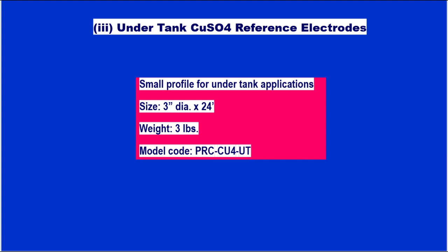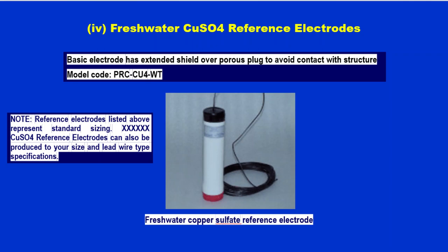The next type is the under-tank copper sulfate reference electrode — small profile for under-tank applications. Size: 3-inch diameter, 24 inches length, weight 3 pounds. Model code: PRC-CU4-UT. The fresh water copper sulfate reference electrode has an extended shield over the porous plug to avoid contact with the structure. Model code: PRCCU4WT. Reference electrodes listed above represent standard sizing; copper sulfate reference electrodes can also be produced to custom size and lead wire type specifications.